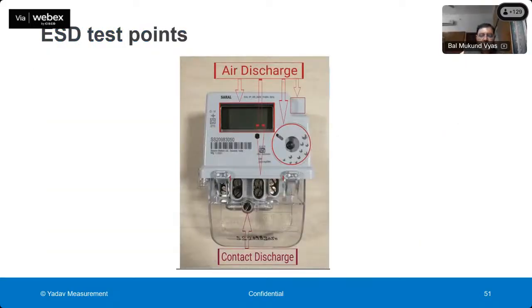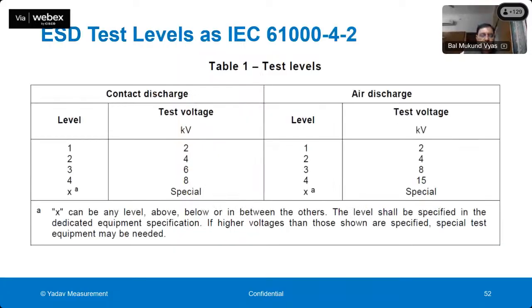So you can see here at various points discharges are applied, air discharge, and if it is a metallic point, then contact discharge is applied. So these are the voltage levels for electrostatics: 2 kV, 4 kV, 6 kV, 8 kV, and the meter has to pass up to 8 kV of contact discharge and 15 kV of air discharge.